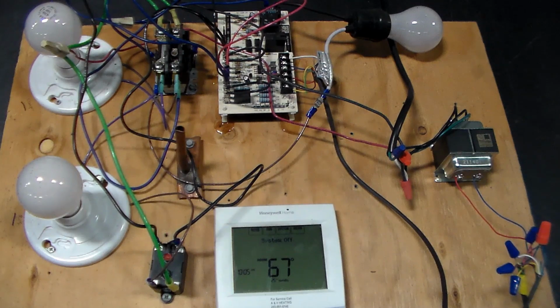But the other thing we do, because we're running in cooling mode, we're basically blowing cold air in the customer's house, or technically removing the heat from the air in the customer's house, and they're going to feel cold air blowing. So the heat pump board will then send the W1 signal back inside to the house to turn on the backup heat to temper the air during defrost, and so the customer doesn't feel cold air blowing. Now, the other thing the W wire does on some of the more modern heat pumps is, some of these more modern heat pumps have an outdoor temperature sensor built into their board. And those are set from the factory at whatever their COP, their balance point is, so that when it gets to a certain cold outside, the heat pump board will lock itself out and send that signal back in on W to run the auxiliary heat. So it'll basically run emergency heat for you.